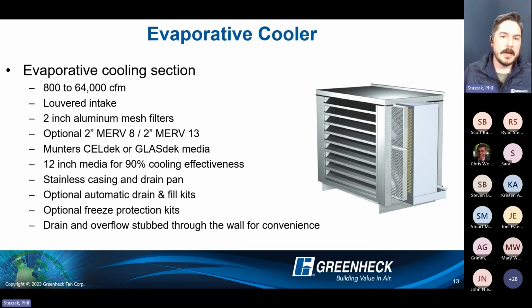bulb temperature is outside. The benefit of evap cooling is airflow is pretty much limitless. You can go all the way up to 64,000 CFM with one single makeup air unit and introduce evaporative cooling. And again, the efficiency stance on this, 90 to 95% cooling effectiveness, depending on that outside air. Now, as a standard, we're going to use Munters CELdek media. GLASdek is available if you need the fire rating as well. So they're really the best in the industry.